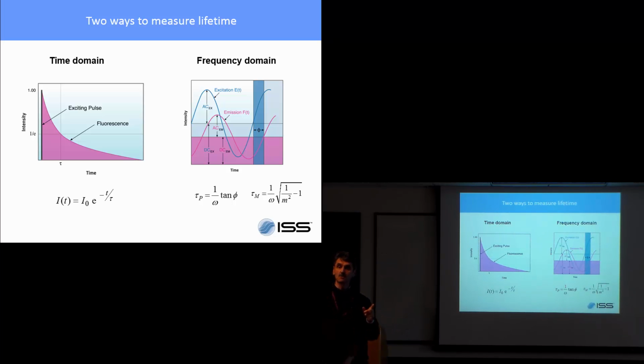If you have 1 nanomolar fluorescein, and then you prepare two other solutions of 10 nanomolar and 100 nanomolar, the intensity varies in each solution and is almost linear within a range. The lifetime is the same. This is one of the reasons that people want to use lifetime, because it is a measurement that is not dependent upon the concentration of the fluorophore.